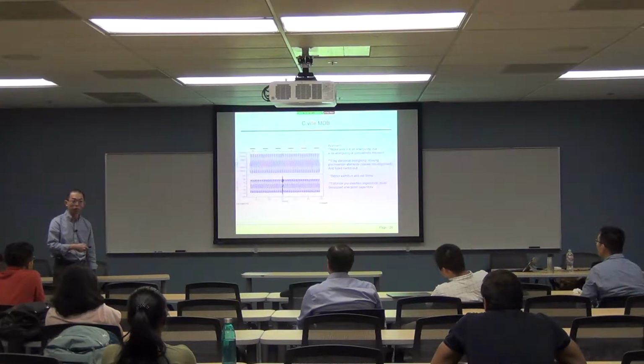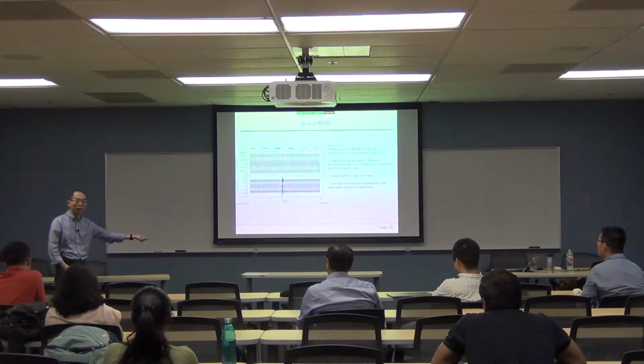The current here is about 100 amps peak. So is this capacitor energizing or not? If you don't know the systems, you might take that into account in your algorithm development. This is what I call sympathetic transients — there's another capacitor bank nearby that is energized, and it couples into the other capacitor. That's why you see this but nothing physically energized here.